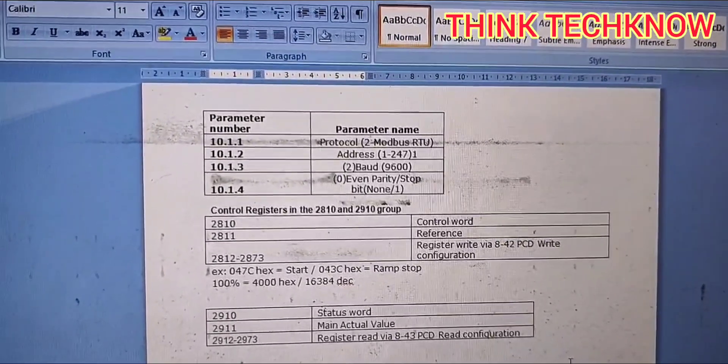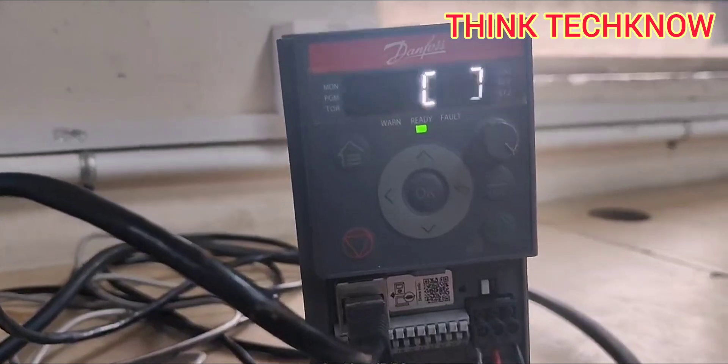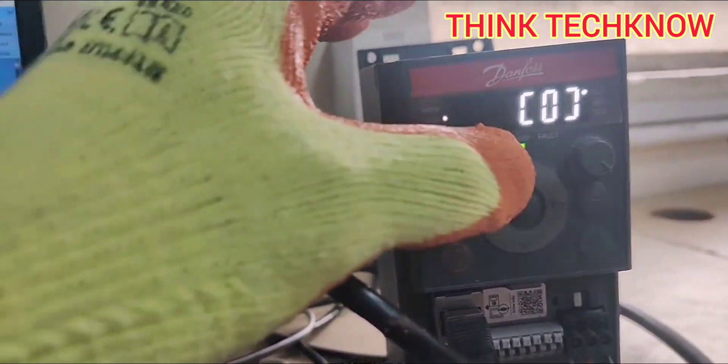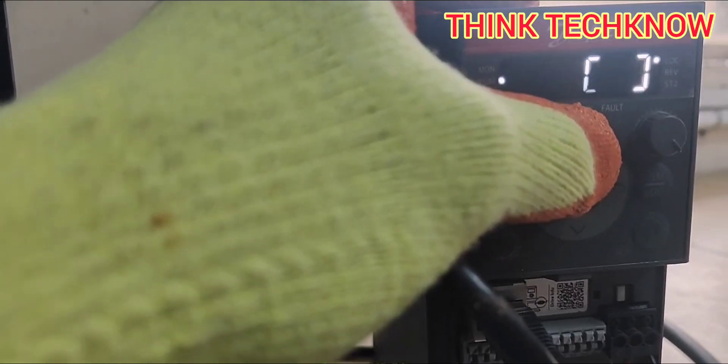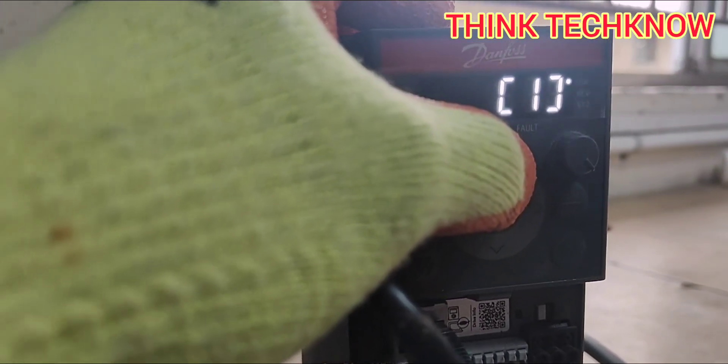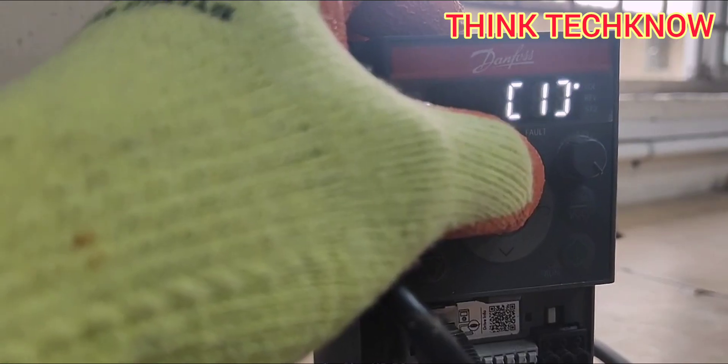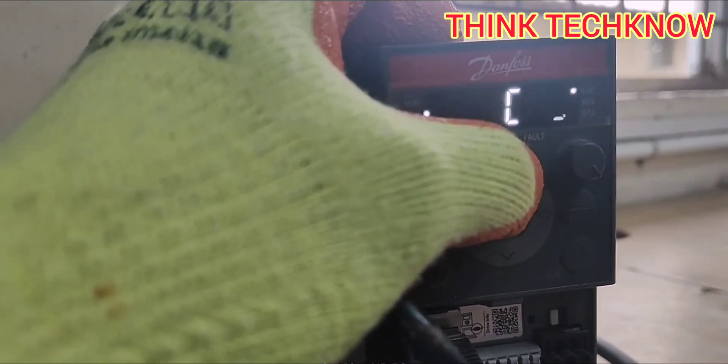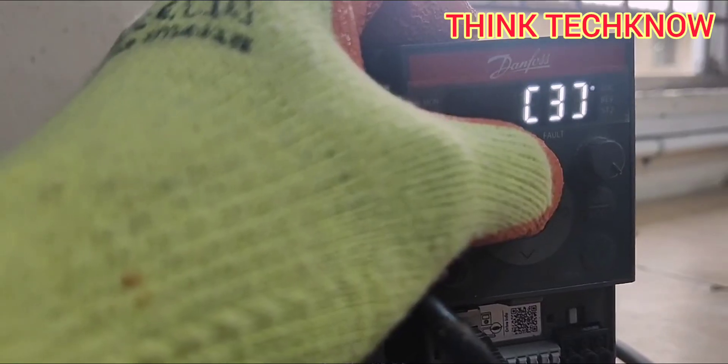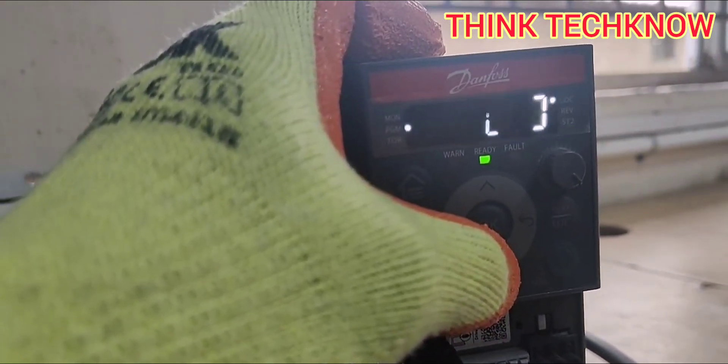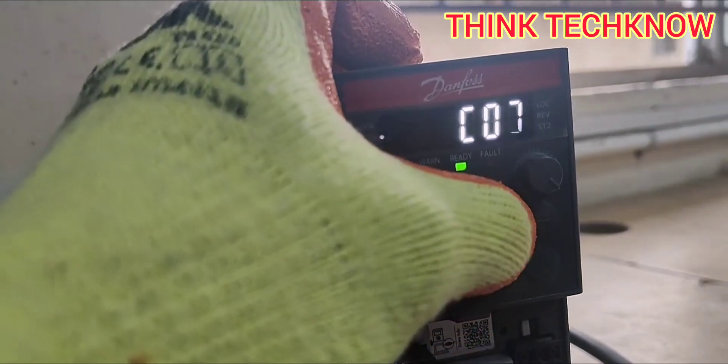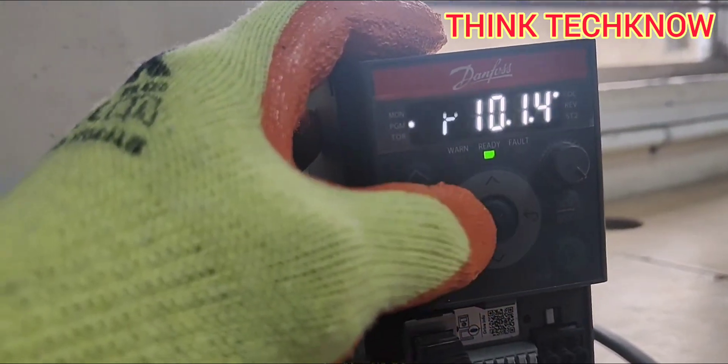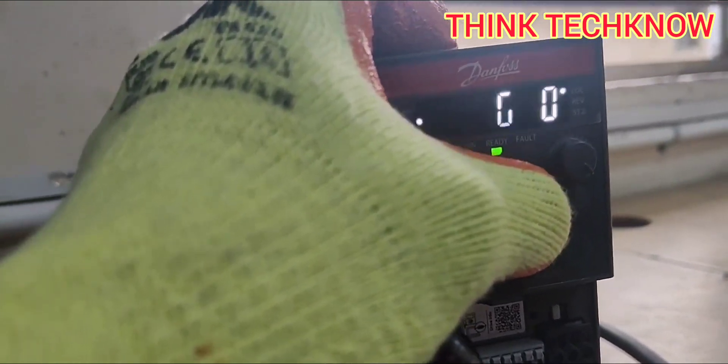And then 10.1.4 is parity. You can select 0 for even parity, 1 for odd parity. Actually, 0 is for even parity 1 stop bit, 2 for no parity 1 stop bit, and 3 for no parity 2 stop bits. Now we are going to select even parity 1 stop bit, so I am selecting 0 here. Press OK button. The value is fixed. That's all the programming.